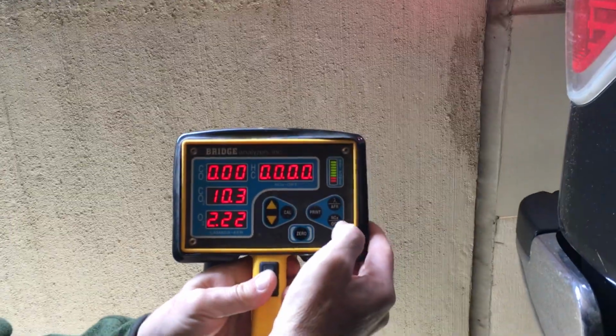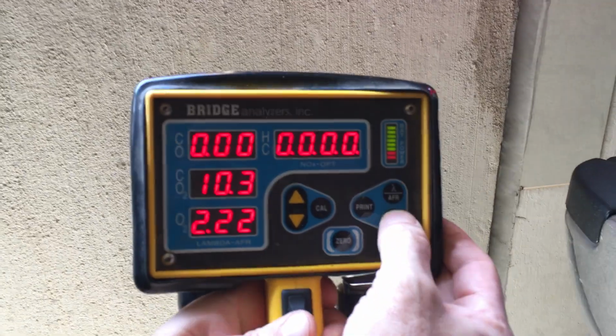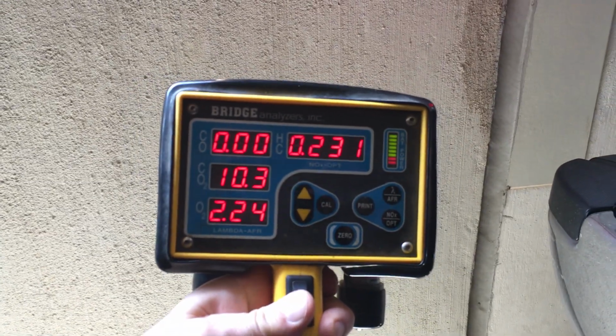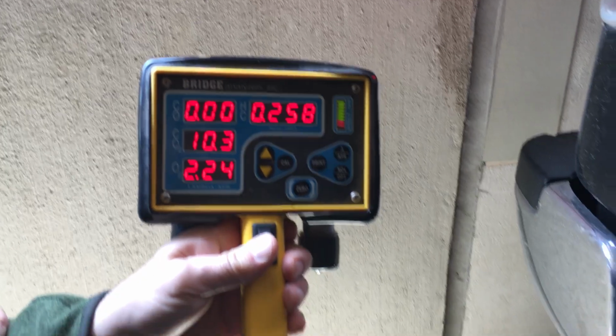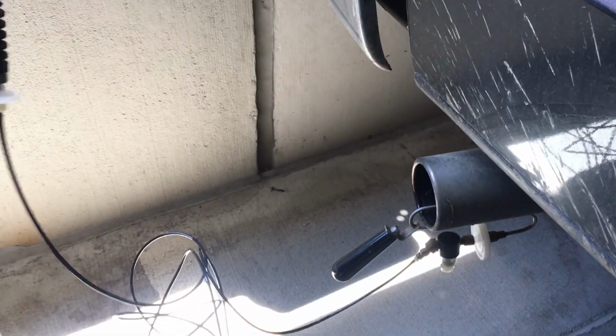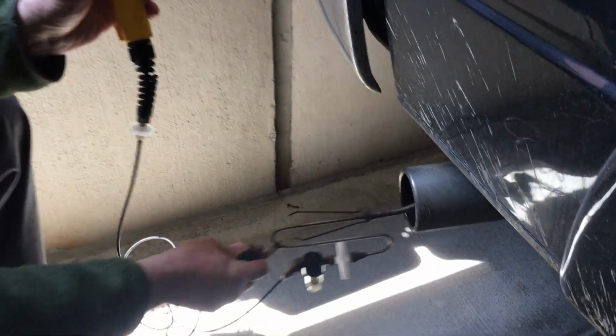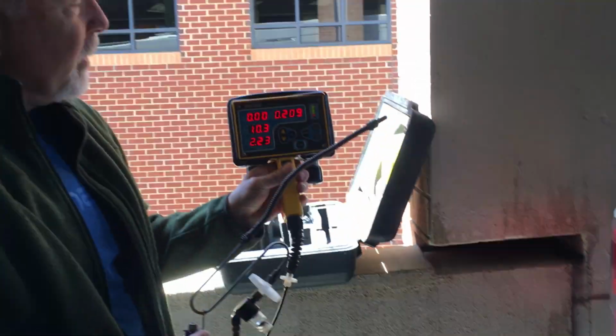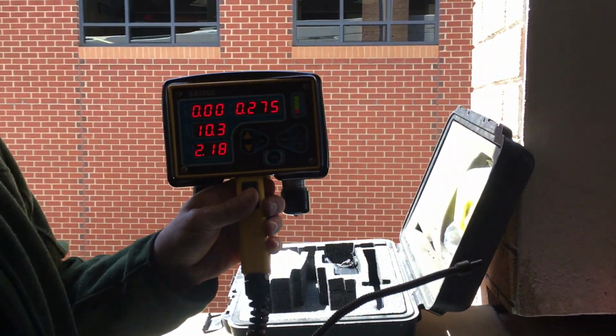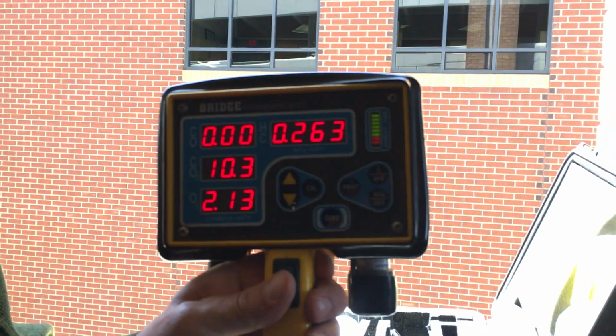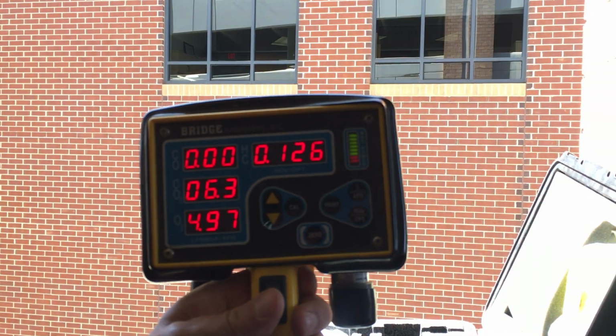So I'm going to go ahead and turn the NOx option back off, and we go back to a hydrocarbon reading, carbon monoxide, carbon dioxide, and oxygen. I'm going to take the unit out of the exhaust. We should have a recovery as this goes back to atmospheric levels of these gases.